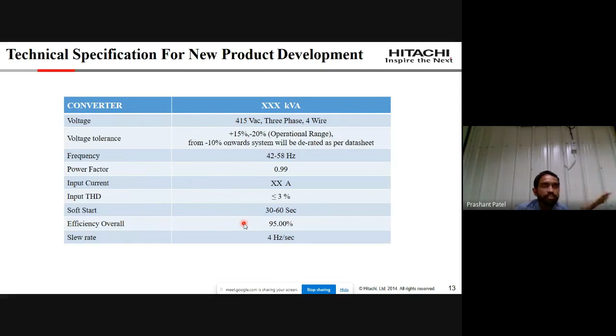Similarly for the slew rate—suppose we're connecting the converter with the grid, and the grid has frequency variation less than 4 hertz per second, still our converter should remain connected properly with the grid. If frequency variation is above 4 hertz per second, you must disconnect your converter for protection purposes. So this is the input specifications.